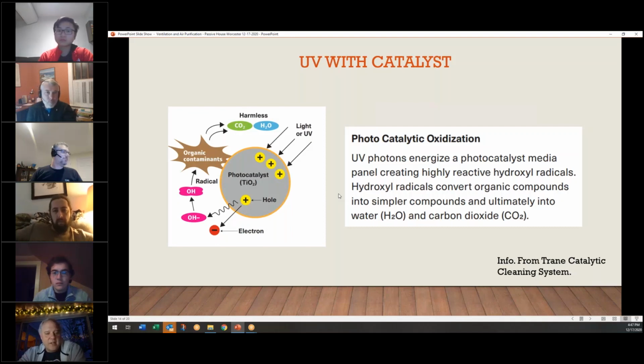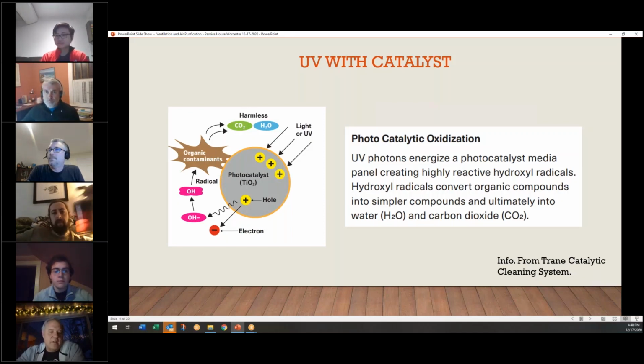So that's something that I've seen. I got this off of the Trane literature. This is something they propose in their much bigger air handlers, like for hospitals. They put this photocatalytic oxidation UV bank in the unit. So the UV light is not only, it's really creating free radicals, if you will, from the catalyst, instead of just relying on the UV light to kill things. So it's kind of doing a dual action. So I just threw that in there.